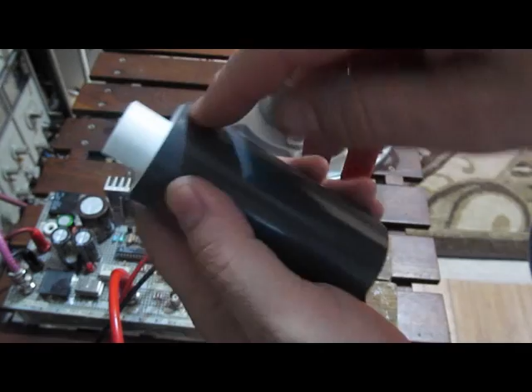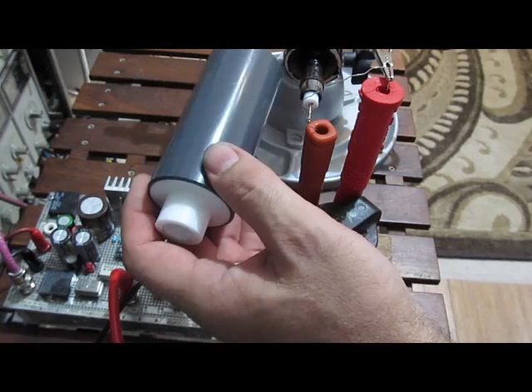Part of the problem with testing this open like this, the end of this insulator is made out of Teflon, and this Teflon inserts down inside the bore of the ceramic tubing. I had anticipated this thing arcing somewhere from the center conductor on up, and there's Teflon on the inside here, but eventually that stops once we get near the resistors. So there's an air section in here where we don't have a lot of protection. The idea is that the Teflon will protrude down inside the tube to add that insulation barrier, so once this all gets assembled, I don't think any breakdown here is going to be a concern.